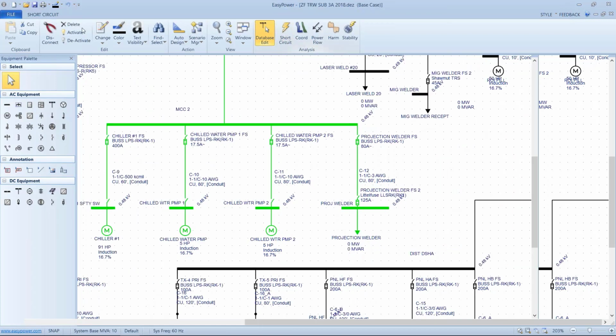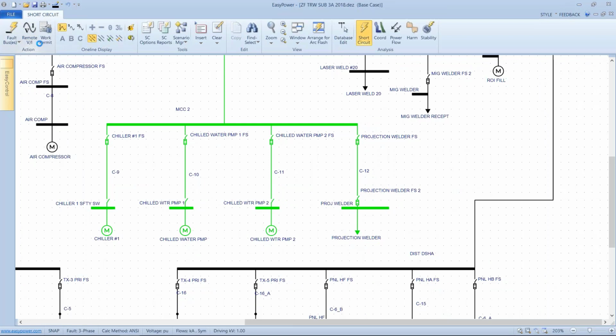I'm going to go to short circuit focus. I'm going to fault all the buses that I've selected, and I don't see anything awry. There's nothing apparently out of line with the currents. But if I go to equipment duty, I see that I have some flags on a couple of devices, but there's no numbers. Now, the point here is we really want to know how the rating for any of these components compares to the actual surge current of a worst case fault. So the fact that we see some flags without numbers associated with them means that there's something fishy.